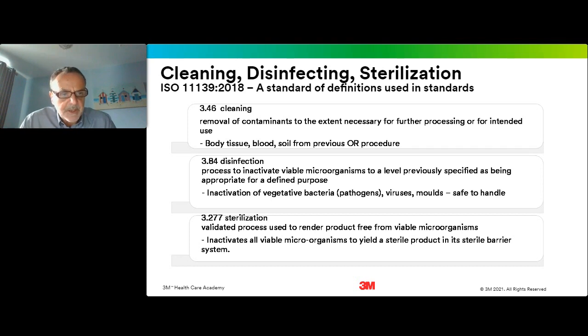The first is cleaning, and cleaning is defined as the removal of contaminants to the extent necessary for further processing or for intended use. Now, that is a relatively vague definition, I think you would agree, because it's suggesting that the level of cleanliness is related to how the instrument will be used. And so really a judgment is then needed to decide what level of cleaning is required, although some national and international guidance documents are now providing some indication of what the level of contamination should be after cleaning.